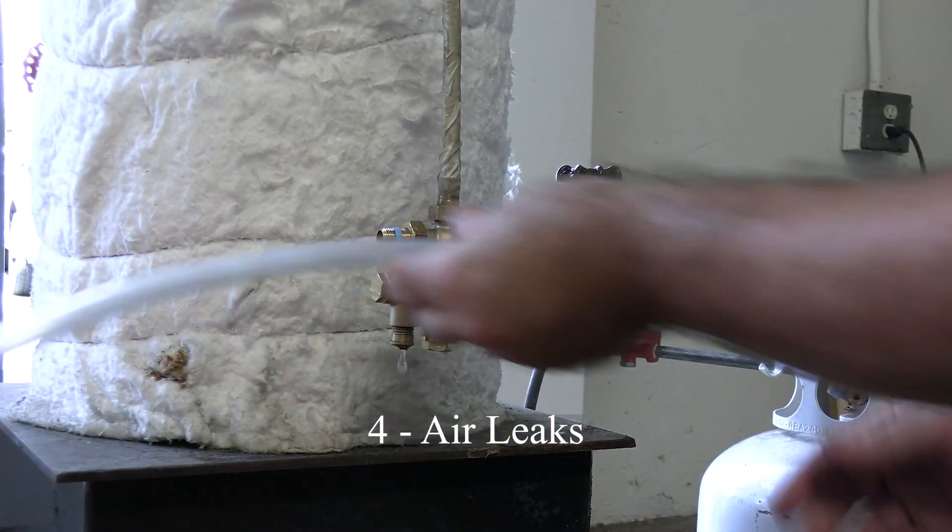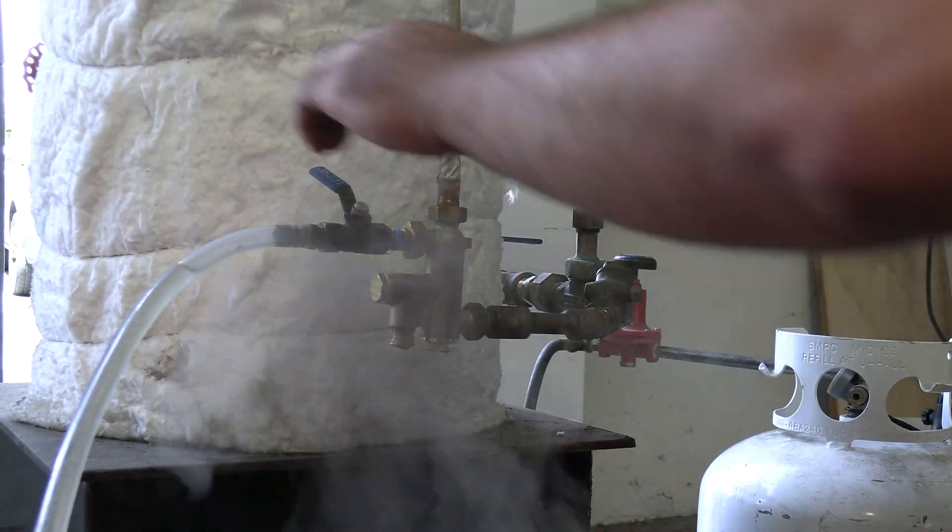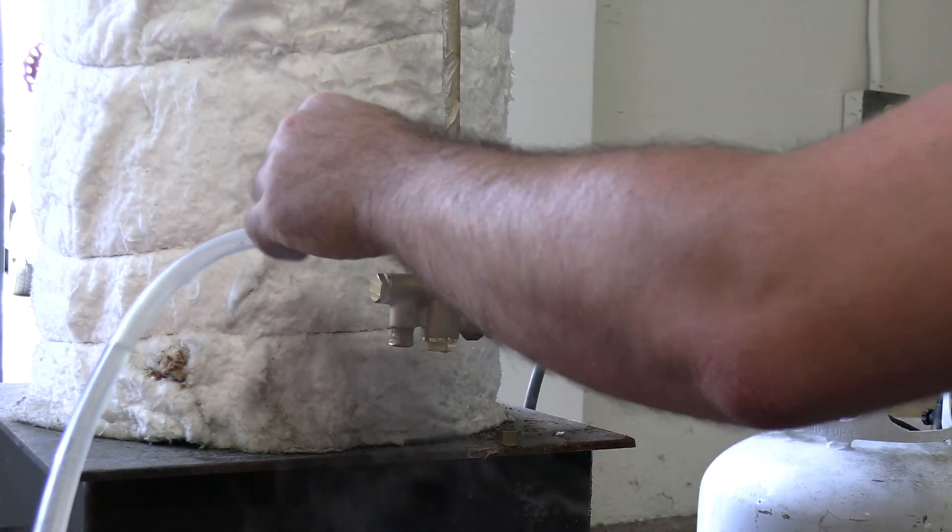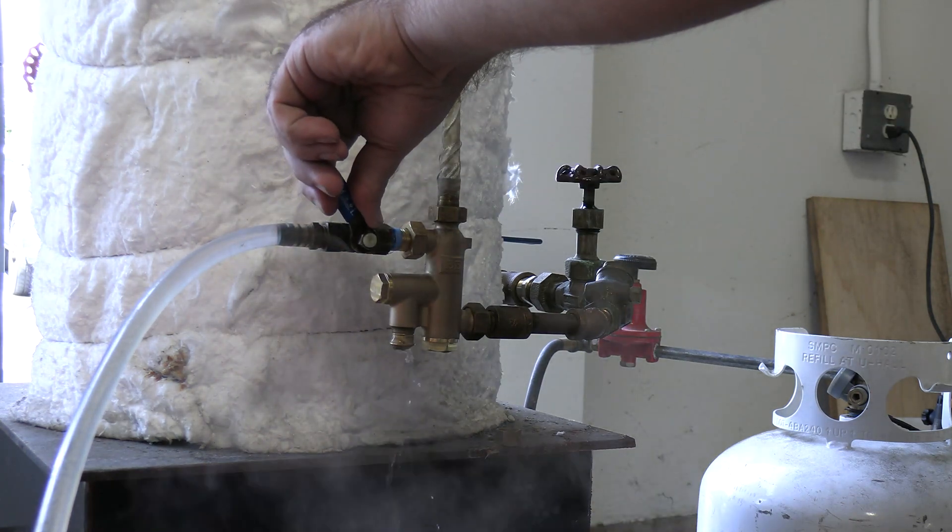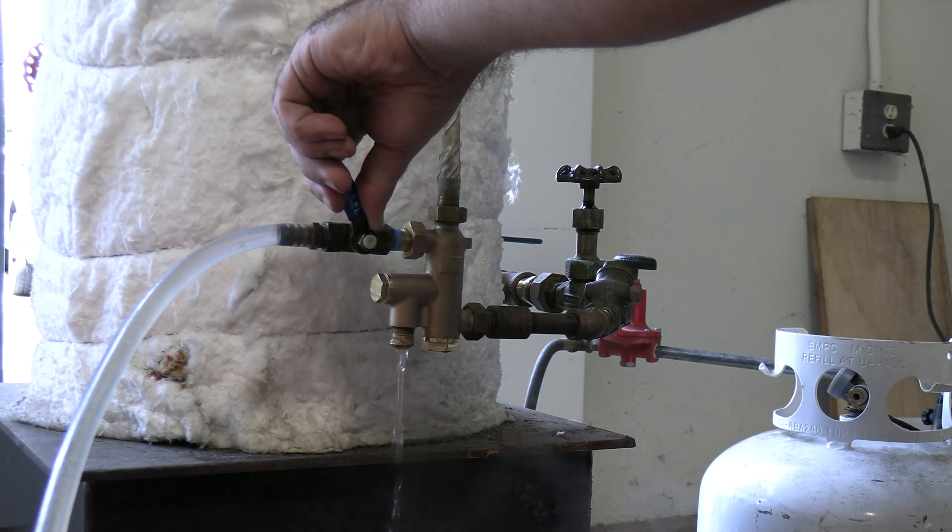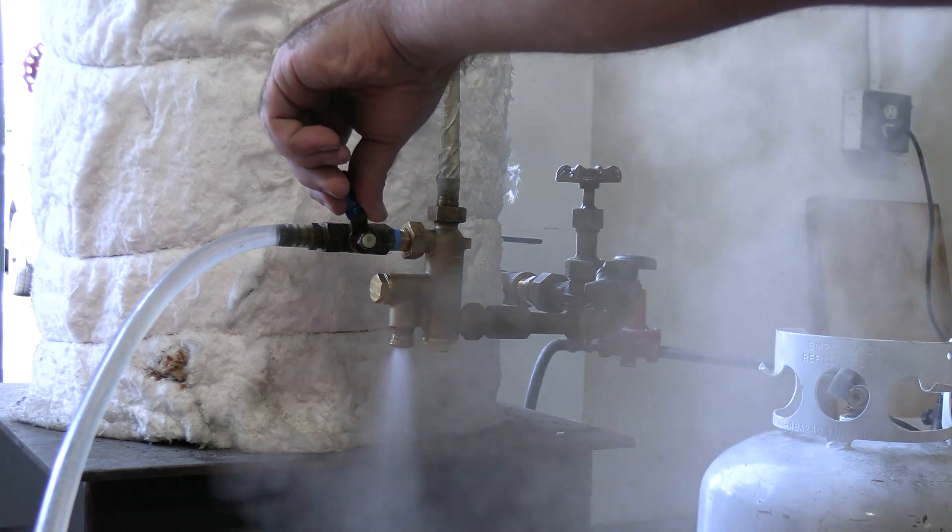One of the most common problems is leaks in the water line. Here I've loosened the fitting into the water valve to simulate that. This is sort of a worst case scenario. Notice it sounds like the injector is trying to start, but the overflow is still leaking, and there is a gurgling sound.